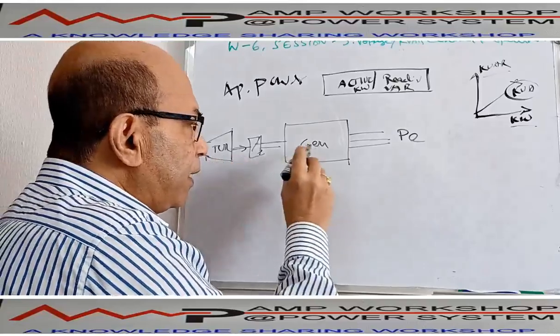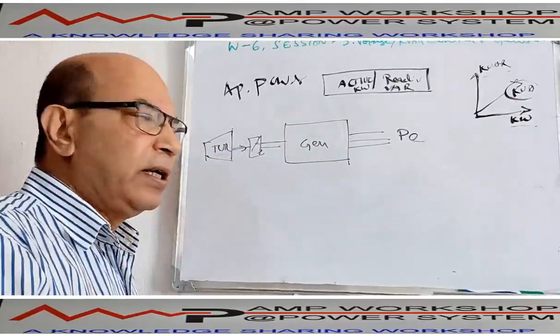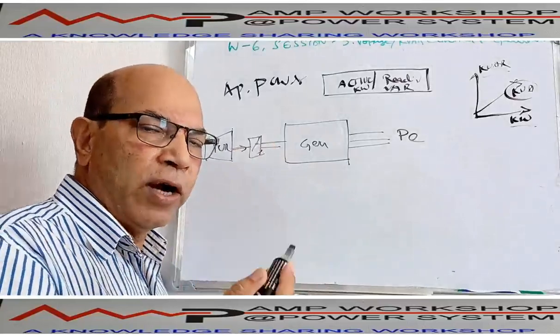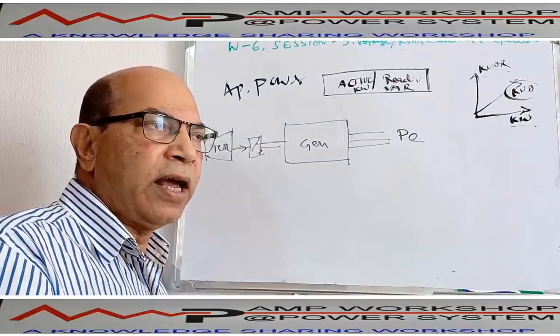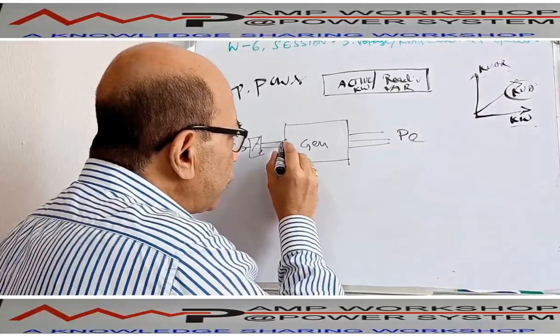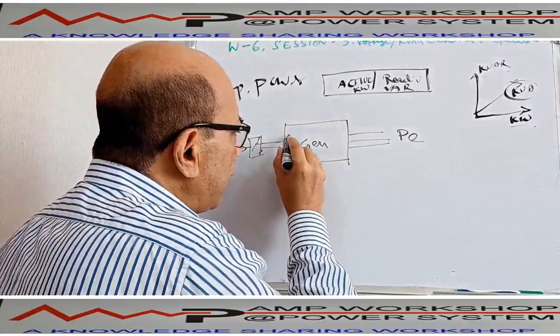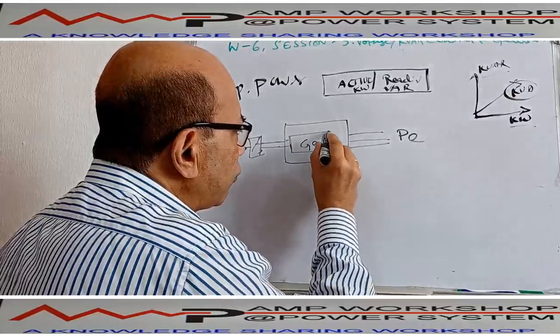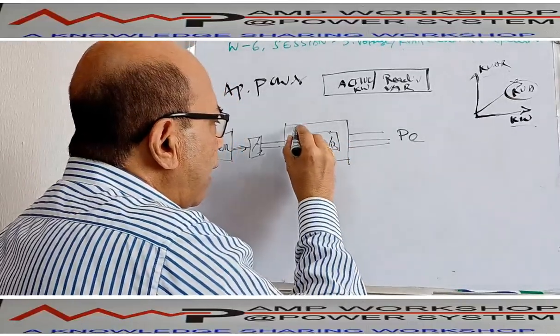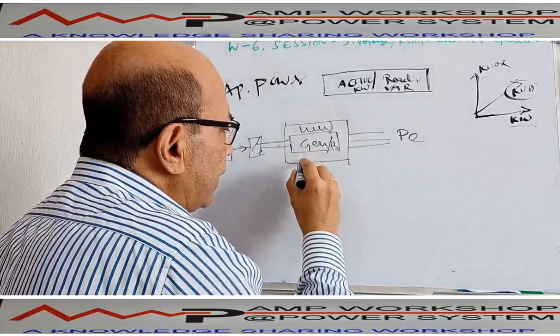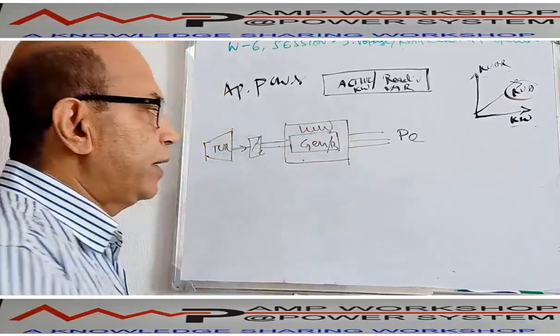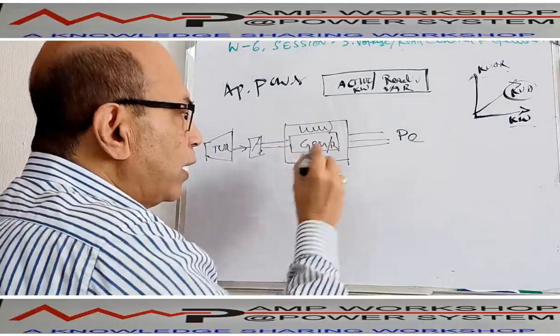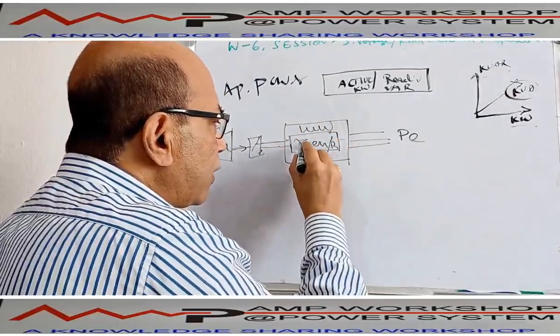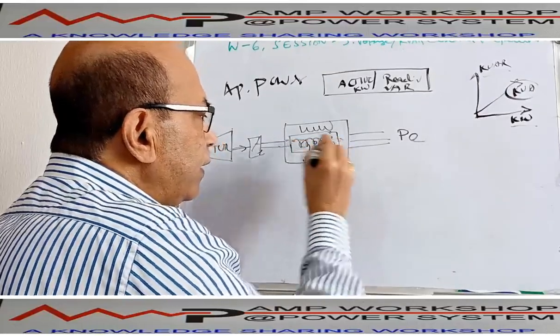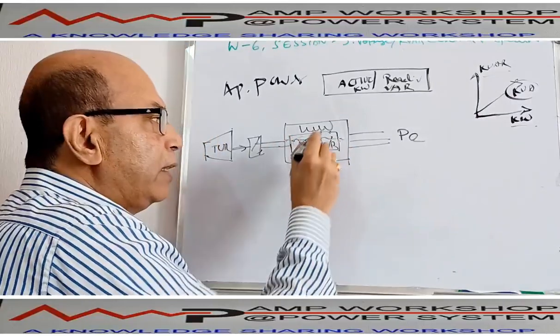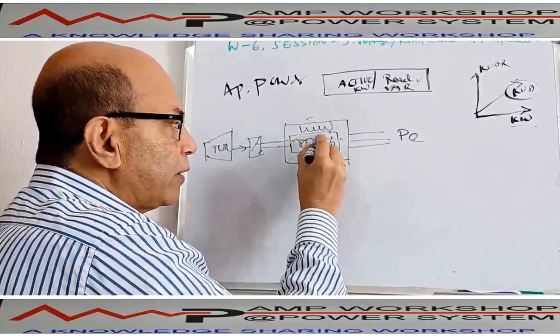Now, in addition to this turbine rotation, the generator has two windings. One winding we call the armature or stator winding, another is the rotor winding. This is my rotor, and the rotor is coupled with the turbine. Outside, there is a winding, that we call the stator winding. This rotor has a winding inside it, and this winding is getting power. This is the stator, this is the rotor, okay?